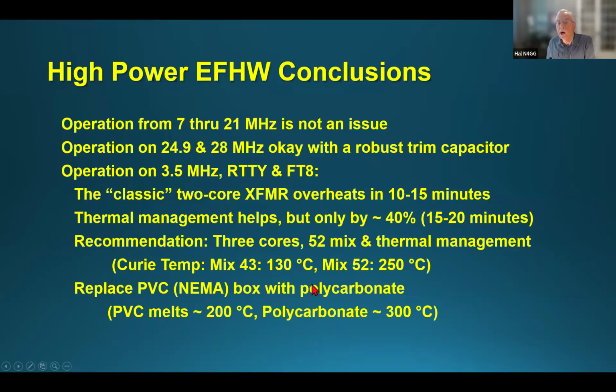But you can buy and you can build special ones that will take all the power. They're expensive. Instead of 2 cores, they use 3 ferrite cores. The ferrite mix is a different mix, which is more expensive. They run them hot. The standard mix starts to fail at 130 centigrade. This more expensive mix fails at 250 centigrade, and they run them up there.